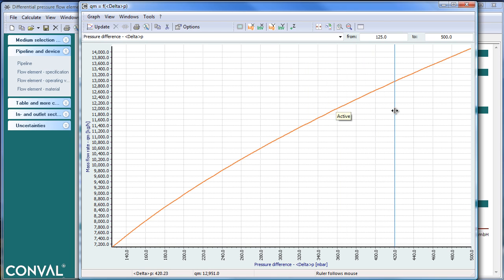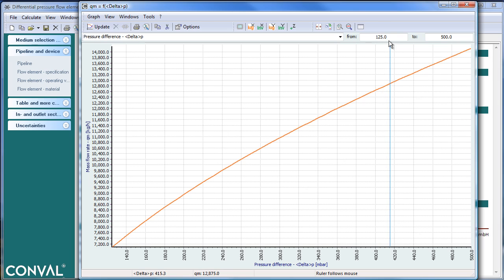Of course, this is a square root curve, which is typical for turbulent flow. Notice, however, the standard range that Conval has chosen is half and double the original value, which was 250 millibar.